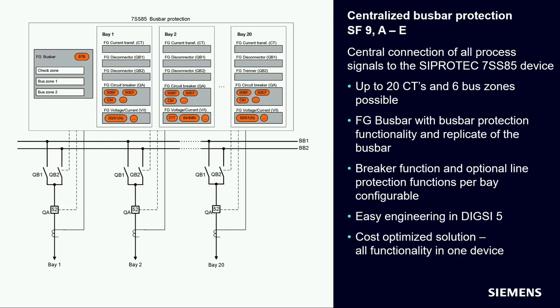In the 7SS85, there is a function group busbar with, in this case, 2 bus zones. Each busbar is 1 zone in this example. If there is, for example, a sectionalizer in the busbar, the number of bus zones is greater. In the function group busbar, the busbar protection algorithms are running: check zone protection, and of course the busbar differential protection algorithms.